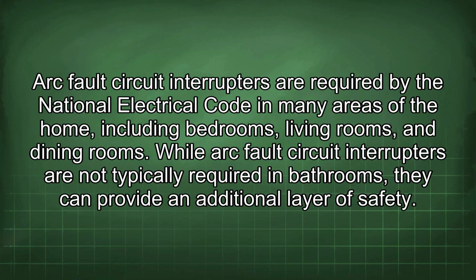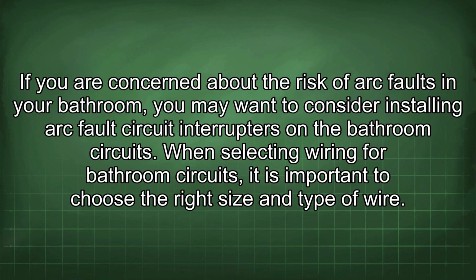Arc fault circuit interrupters are required by the National Electrical Code in many areas of the home, including bedrooms, living rooms, and dining rooms. While arc fault circuit interrupters are not typically required in bathrooms, they can provide an additional layer of safety. If you are concerned about the risk of arc faults in your bathroom, you may want to consider installing arc fault circuit interrupters on the bathroom circuits.